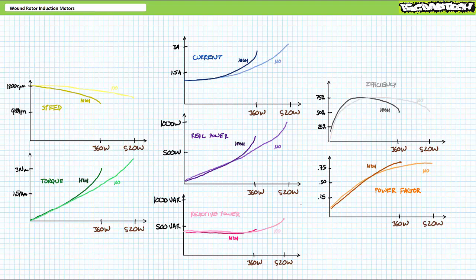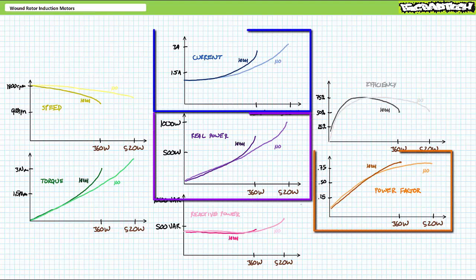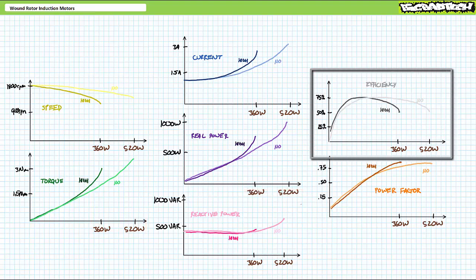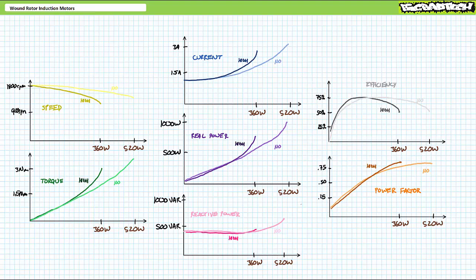Plots of current, real and reactive power, efficiency, and power factor for the no and high resistance configurations also exhibit recognizable behavior. As mechanical power goes up, so does current, real electrical power, and power factor. For this limited range, reactive power remains relatively constant, only rising at the very end. Efficiency peaks out at or near the rated condition. I'm encouraging you to pause the lecture and stare at these plots as long as necessary to confirm your expectations, given your previous experience with squirrel cage induction motors.